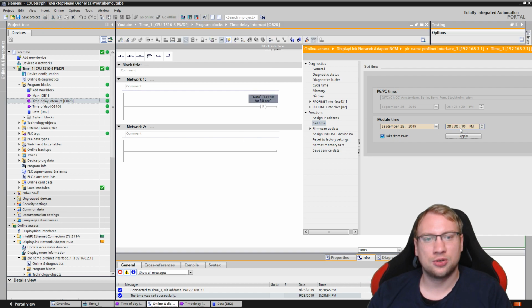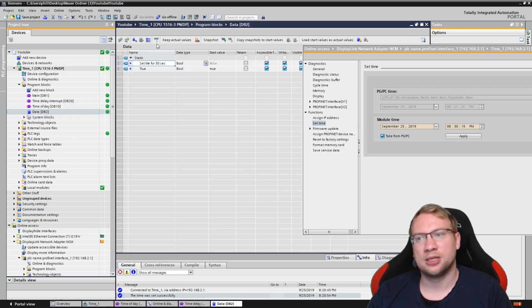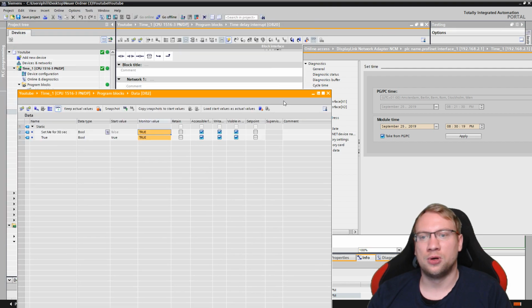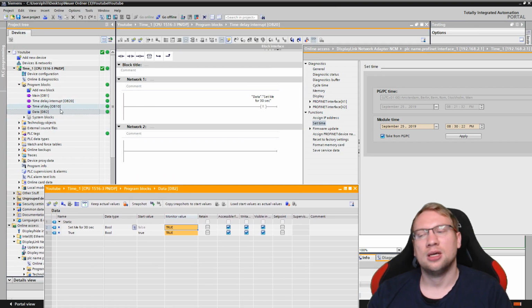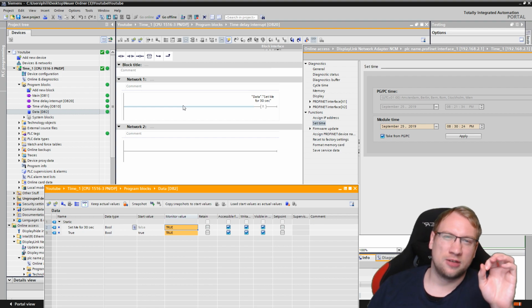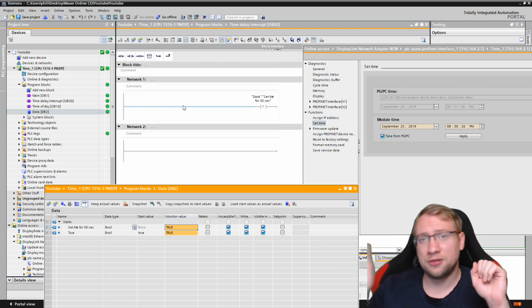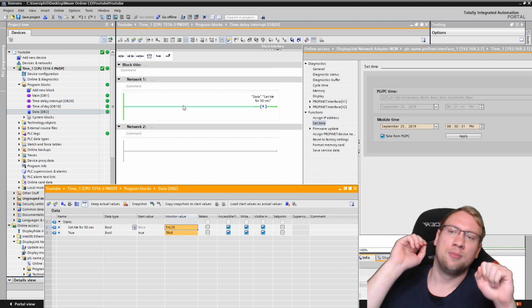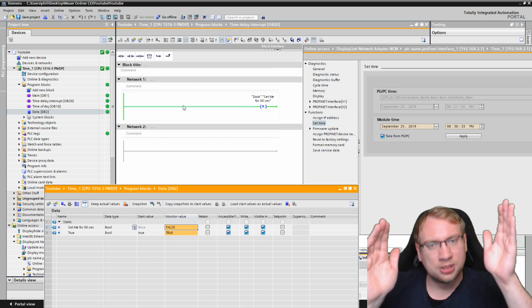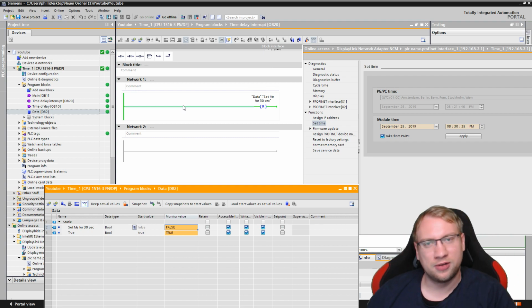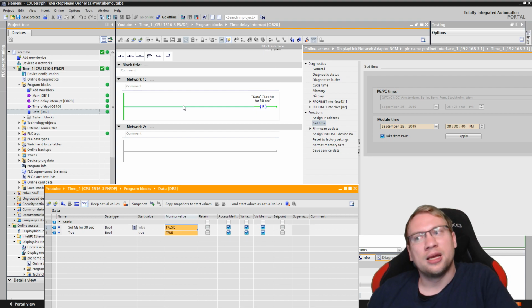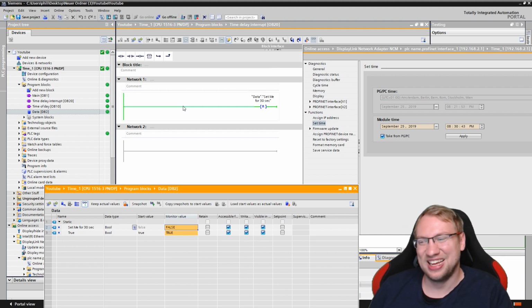After 30 seconds, so exactly when this is 30, the variable will be reset. So right now the variable is actually true, right? Here we have it, it's true, and it will be false in exactly 12 seconds. So we build ourselves a timer now that starts at a specific time of a day. You can make that every day. Check out the video on time of day interrupts. And it will be reset at a certain time afterwards. So a very, very flexible and easy timer, actually. One that I actually like very much.